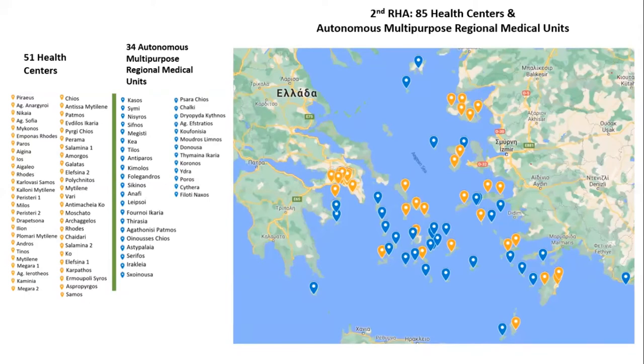After that, this whole region was divided into sectors, and each biomedical engineer visited every sector, island by island, municipality by municipality, health center by health center, and finally room by room, they registered every electrical medical device.